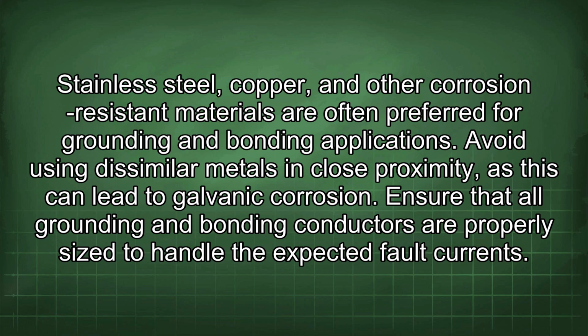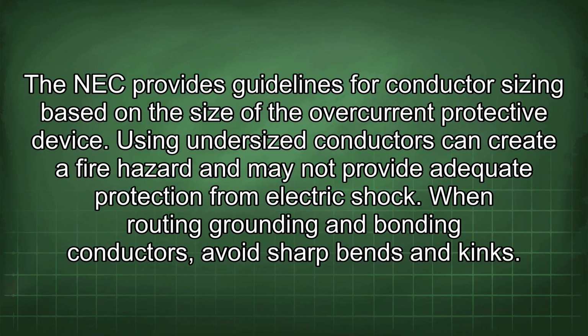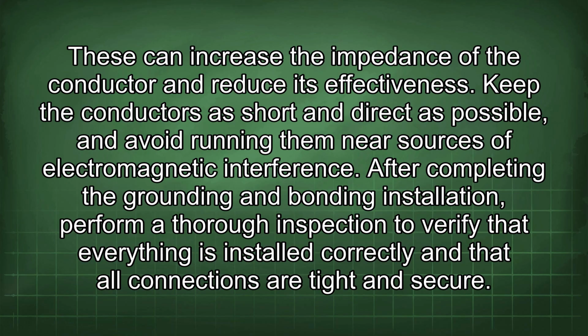Ensure that all grounding and bonding conductors are properly sized to handle the expected fault currents. The NEC provides guidelines for conductor sizing based on the size of the overcurrent protective device. Using undersized conductors can create a fire hazard and may not provide adequate protection from electric shock. When routing grounding and bonding conductors, avoid sharp bends and kinks. These can increase the impedance of the conductor and reduce its effectiveness. Keep the conductors as short and direct as possible, and avoid running them near sources of electromagnetic interference.